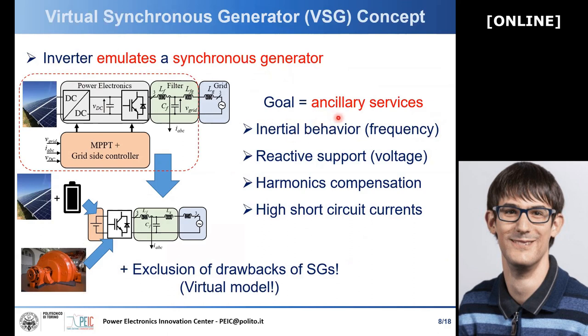Especially, we can provide inertial behavior — so support to the frequency — reactive support to sustain the voltage, harmonic compensation, and higher short-circuit currents. Moreover, since we are dealing with a controller strategy and not changing the hardware, we can implement virtual models which can even be better than synchronous generators, because we are dealing with an ideal model, not physical machines with physical constraints. So we can eliminate some of the drawbacks of synchronous generators.